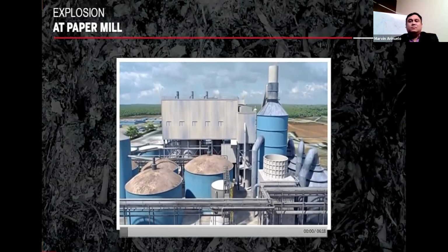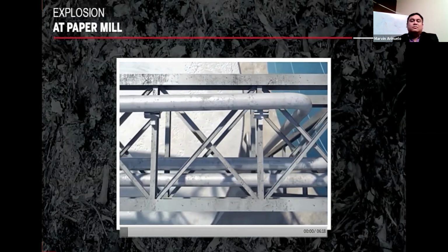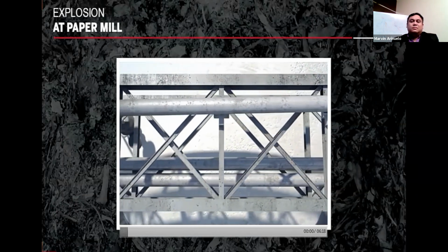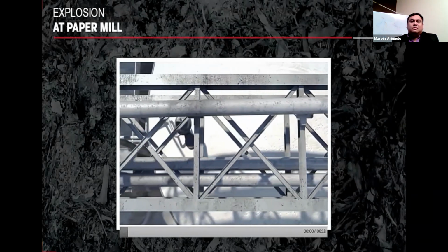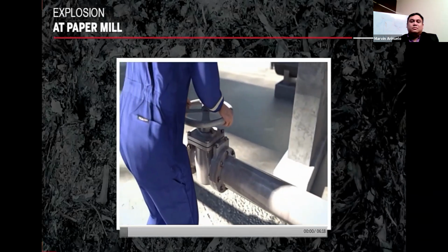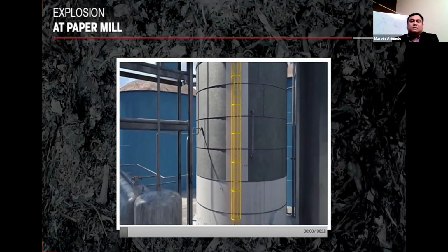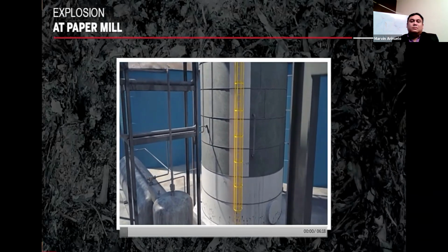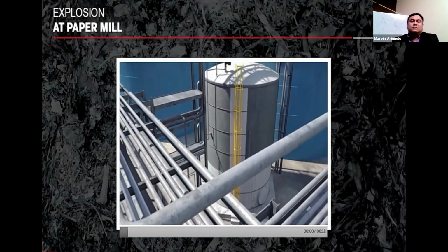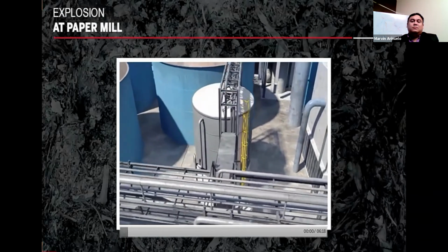One of these tasks was the repair of water piping, located above and connected to the foul condensate tank, that had shifted and cracked months earlier. The repair required welding on the piping, commonly referred to as hot work. In preparation for the hot work, valves were closed leading into and out of the foul condensate tank, while 10 feet of liquid remained inside. The liquid was left within the tank partially because there were no plans to work directly on the tank during the outage. The company also assumed that the tank contained mostly water, was sealed off from the atmosphere, and did not pose a safety risk.